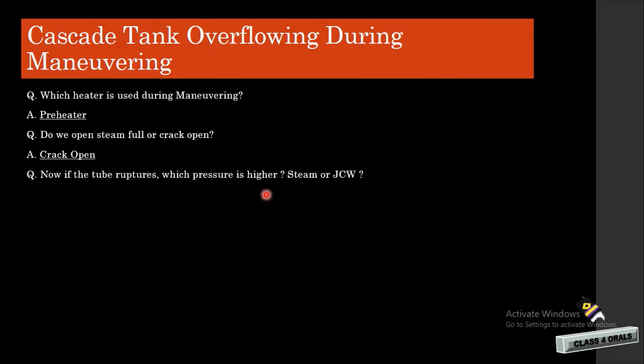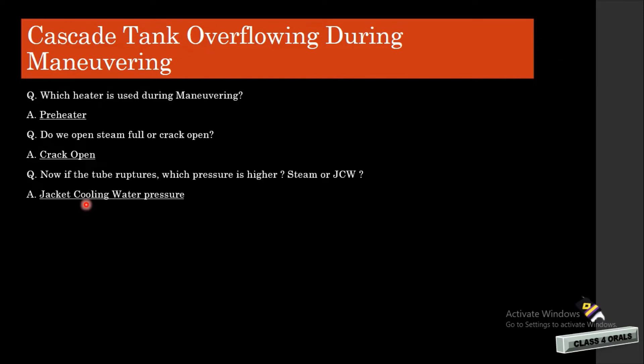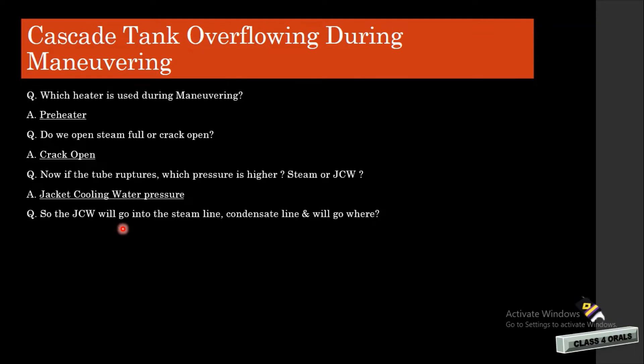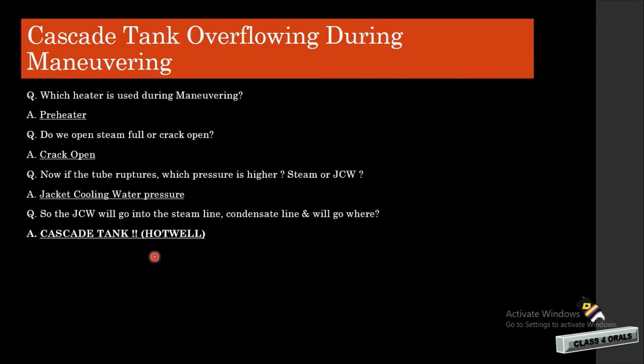Then which pressure is higher — the steam pressure or the jacket cooling water pressure? It is the jacket cooling water that has higher pressure. That means the jacket cooling water will mix into the steam line, and then through the condensate line, it will reach the cascade tank, or what we call the hot well. The cascade tank will start overflowing because of the surplus quantity of jacket cooling water entering.